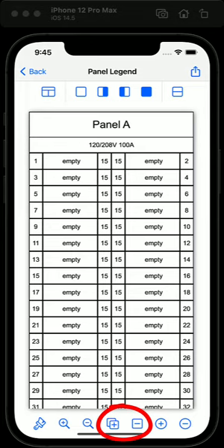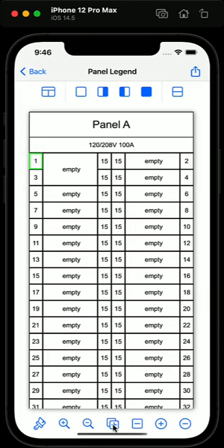Simply select the circuit you want to adjust and click the plus button once to create a 2-pole breaker. Pressing again will create a 3-pole breaker. By selecting the first circuit in a multi-pole breaker and pressing the minus button, you can revert that breaker back to less poles. You can also adjust multiple selected circuits at once. For example, let's create 3 2-pole breakers. I will select circuits 1, 5, and 9, and then press the poles plus button. Now we have 3 2-pole breakers.